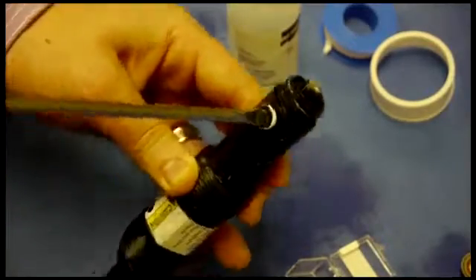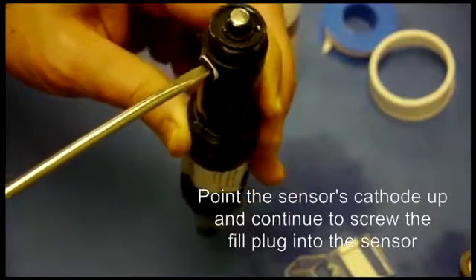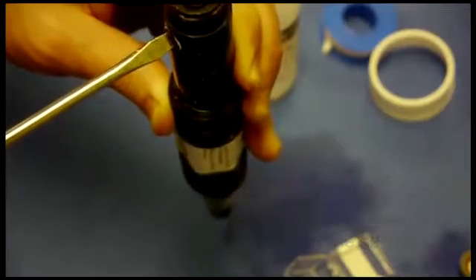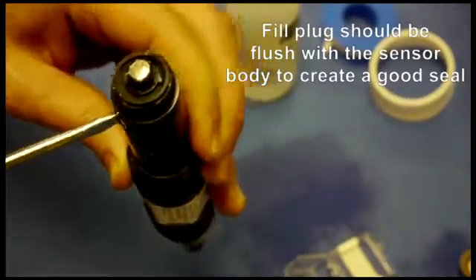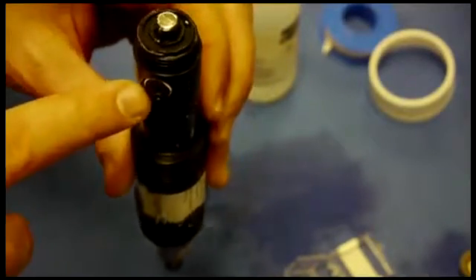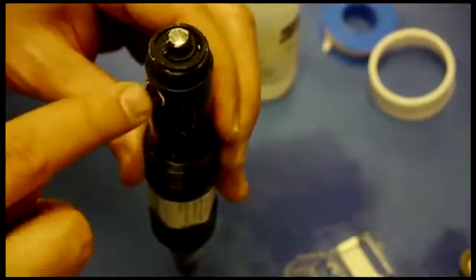After a few turns, turn vertical. Slowly turn, and this will test the seal and also make sure everything is in straight. Tighten it just enough to get the sensor to be flush with the fill plug. Don't overtighten - that's the key. Overtightening will actually crack the tip of the probe. All you want to do is create a good seal.